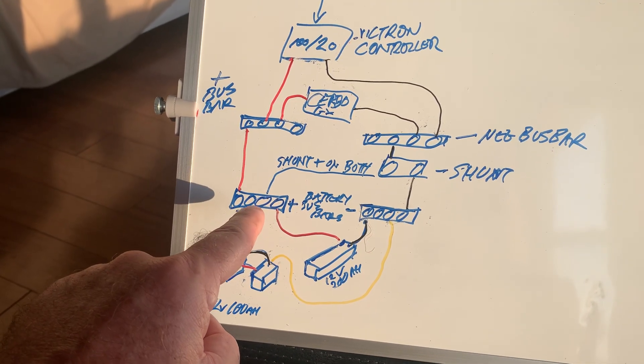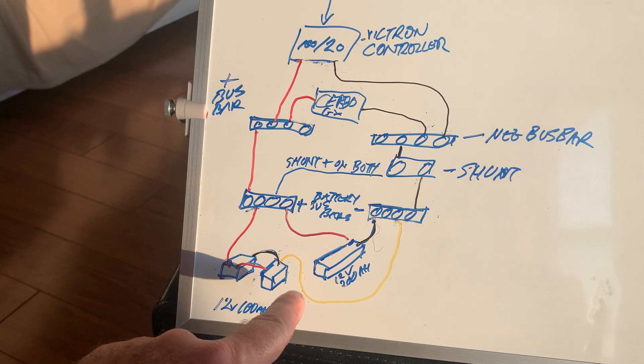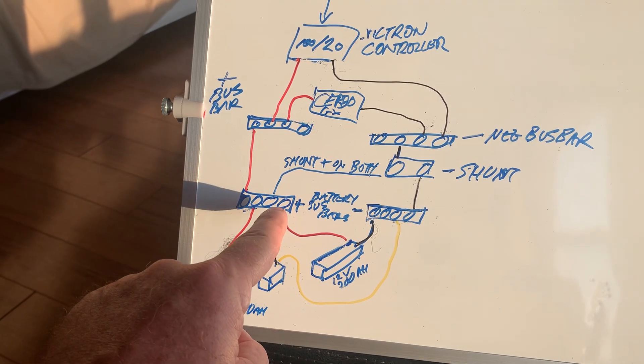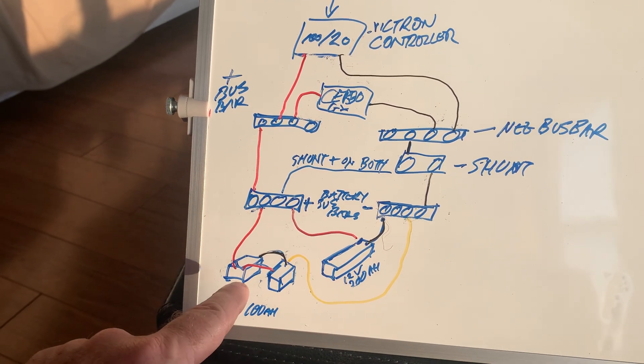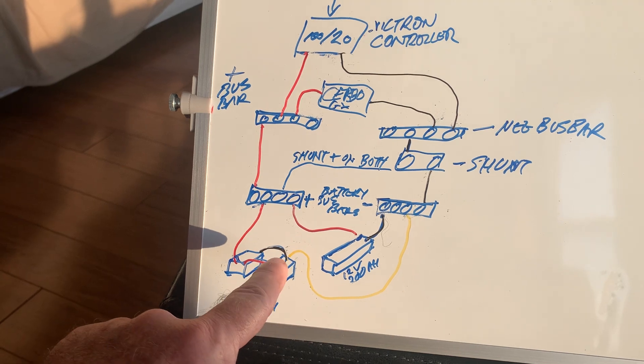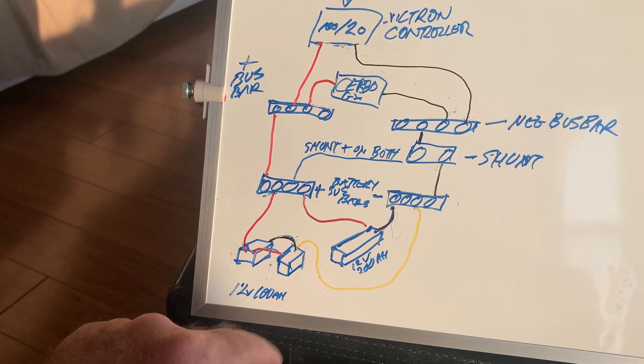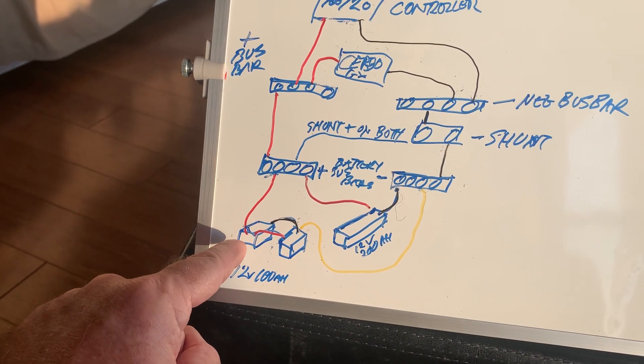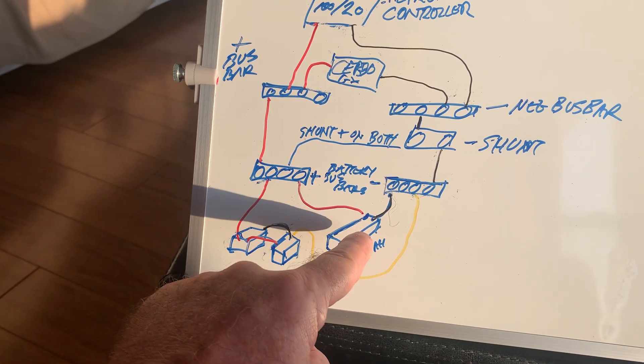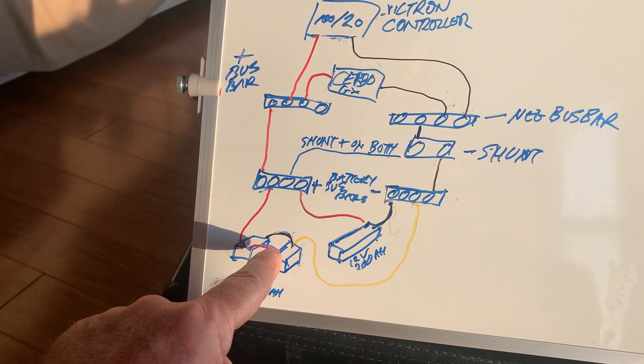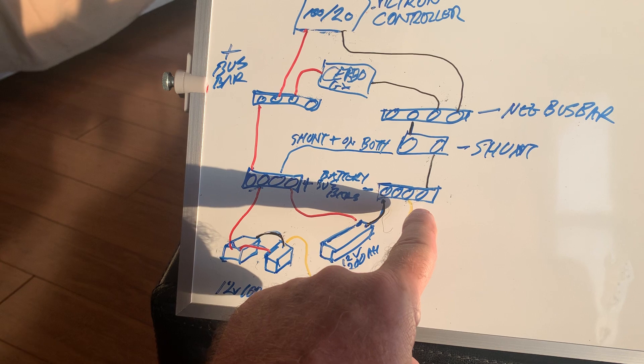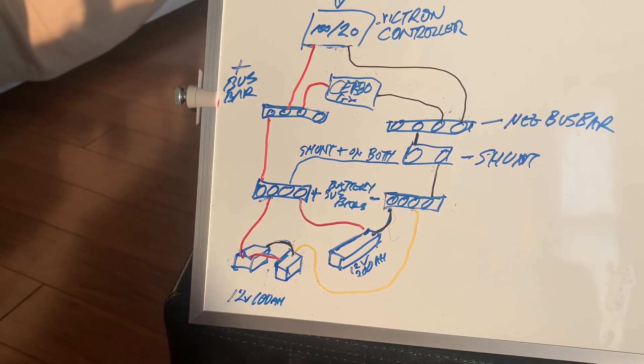Their negative will go to the new negative bus bar, sharing that with the old battery. Then I'm going to move this positive from the shunt. Instead of going directly to this battery, I'm going to bring it over here so it's getting a reading from this battery bank and this battery bank.